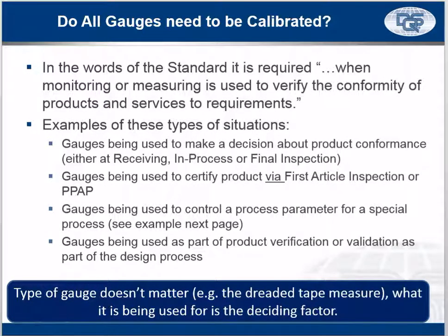First of all, do all gauges need to be calibrated? This is always a question when we talk about this requirement of the standard, because you'll walk through a factory and you'll walk up to a control panel and there'll be hundreds of gauges on it. And the question is always, does this need to be calibrated? Or you'll see somebody using a tape measure to make an inspection. There's always a discussion about whether tape measures need to be calibrated. And here are your rules for determining whether something needs to be calibrated or not according to the standard.